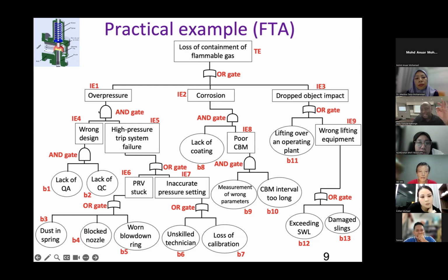But for the AND gate, these 2 must happen together for you to have overpressure. So 1, there must be wrong design, and there must be high pressure trip system failure. Because if your design is wrong and your trip system works, then you will not have overpressure. Even if your design is wrong, once the pressure begins to rise, this trip system will cut off the system. So there will not be overpressure. So these 2 must happen simultaneously for this to happen. And that's how you keep going until you get to this oval shape or circle shape. Once you get to this stage, you have come to the end of that branch. This is referred to as basic events. So basic events are your root causes.